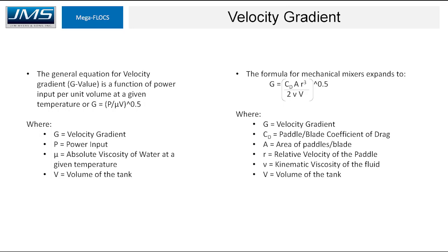The formula expands a little bit when we're dealing with mechanical mixers. The power input is made up of the coefficient of drag, area of your paddle or mixing blade, and the relative velocity between that blade and the water. The paddle area and speed are the easiest variables to adjust, so that's typically how we achieve a tapered velocity between stages in a flocculation basin, by varying the area and speed of the paddles.